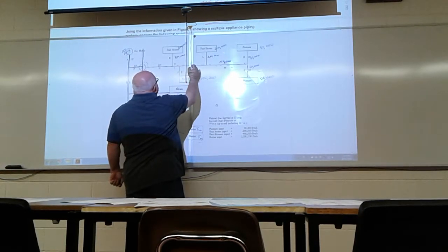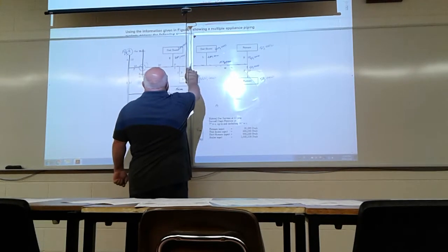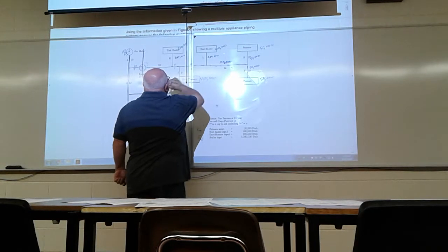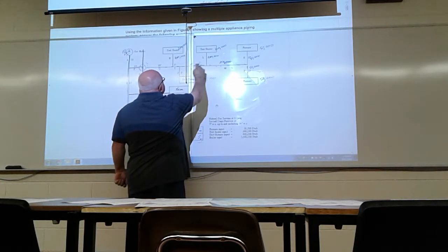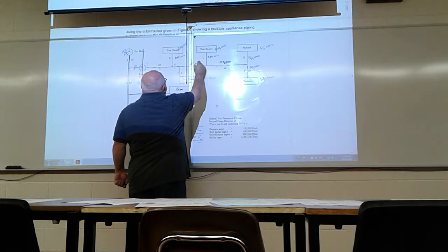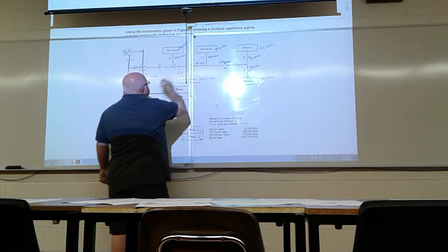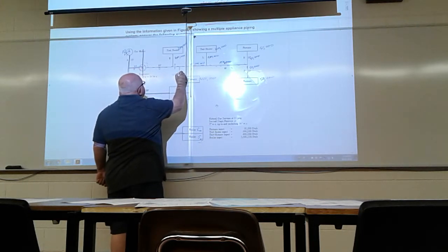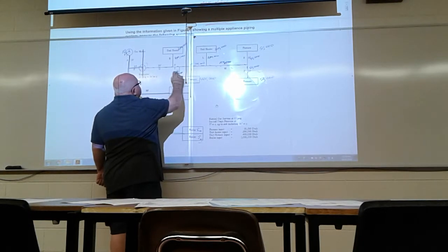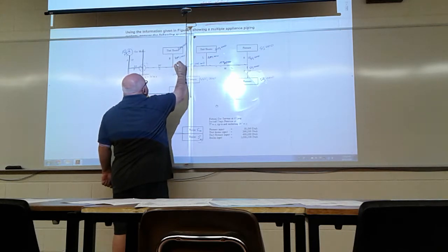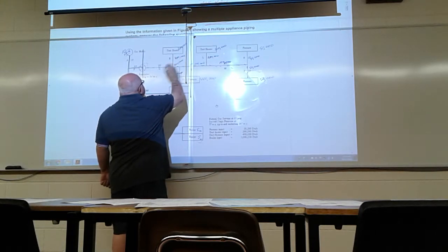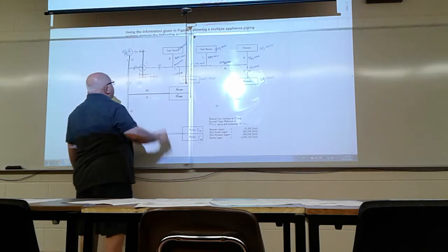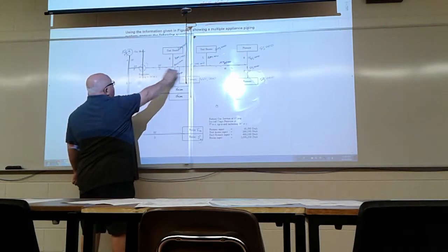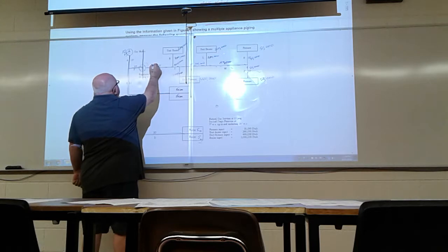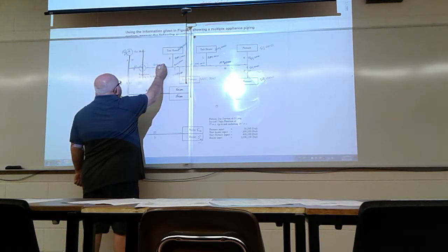Okay, so as I go on to this one right here, K, it's going to be 100,000 plus 200,000, so that's going to be 300,000. Okay, pipe J only has to handle the duct furnace at 400,000. Pipe I has to handle everything, the 300,000 and the 400,000, so 700,000. Okay, again, pipe H only has to supply itself, and pipe G has to supply everything on the low pressure side, so you are looking at 900,000 BTUs.